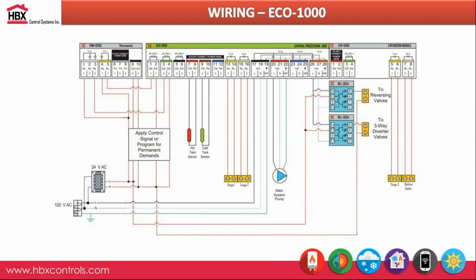The last 3 relays are line voltage rated for 240 volts at 10 amps on the 1000. It's also 10 amps on the expansion modules. Pins 5 and 6, 7 and 8 on the expansion module is where you wire up your third stage of your heat pump. That last relay could be for your stage 4, but for this example we're utilizing a backup boiler, so that's where you would wire up the backup boiler in terms of sequence.